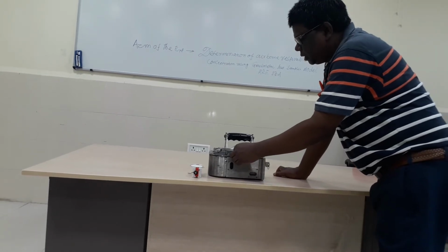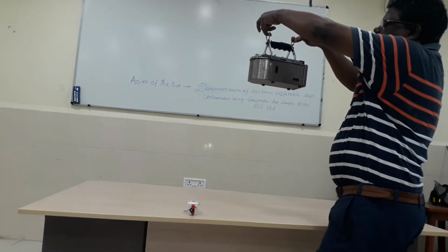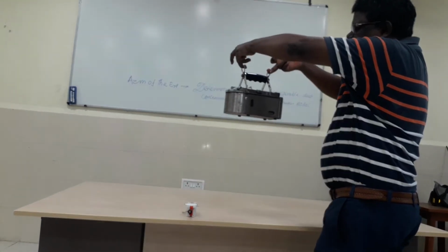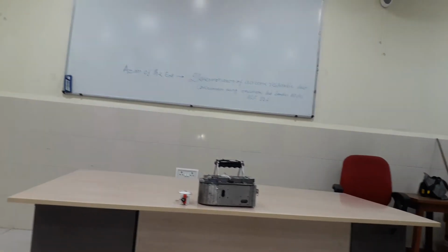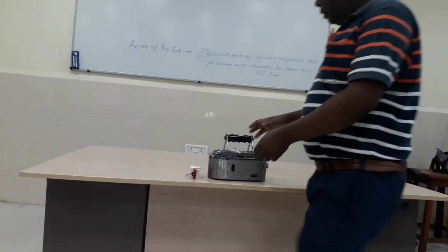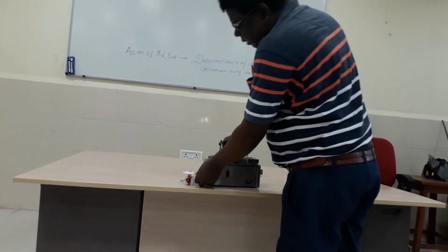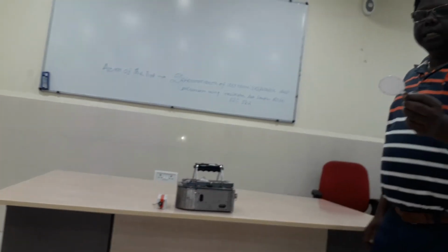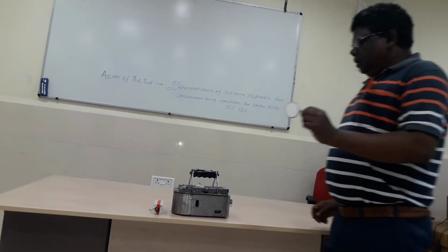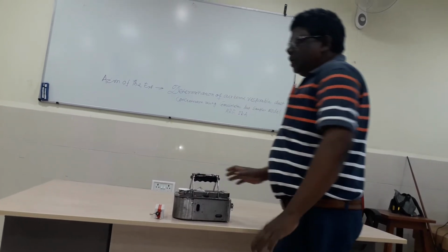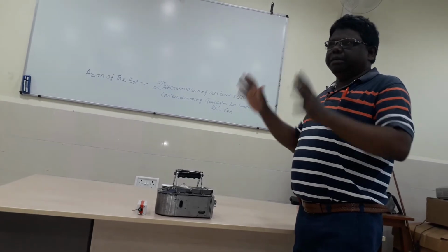Then we start the on off switch, and hang the instrument at nose level in the return of the working district. We will run it for the full shift, that is 8 hours. After that, it is stopped and removed. Then remove the filter paper and take the final weight. The difference in filter paper weight gives you the dust deposited on the filter paper.